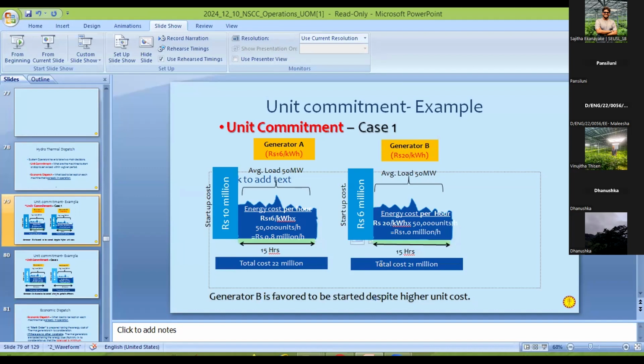So that's what you have to understand: merit order does not simply mean operating power plants from least cost to highest cost. We have to consider many things. For example, if you recalculate without the 15 hours time period, the figure will change, shifting the choice from generator B to generator A. There will be a break-even point depending on this time period. So in unit commitment, you have to consider the startup cost, the time duration, and the unit cost. Only by considering all three parameters can you decide which option is the least cost one.